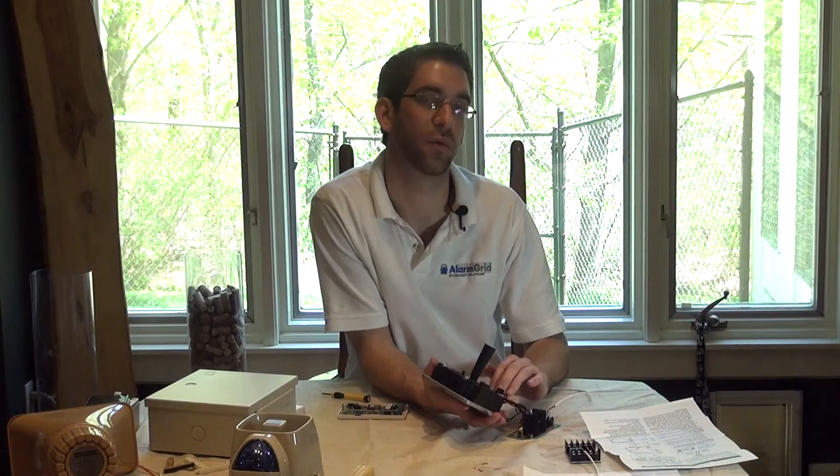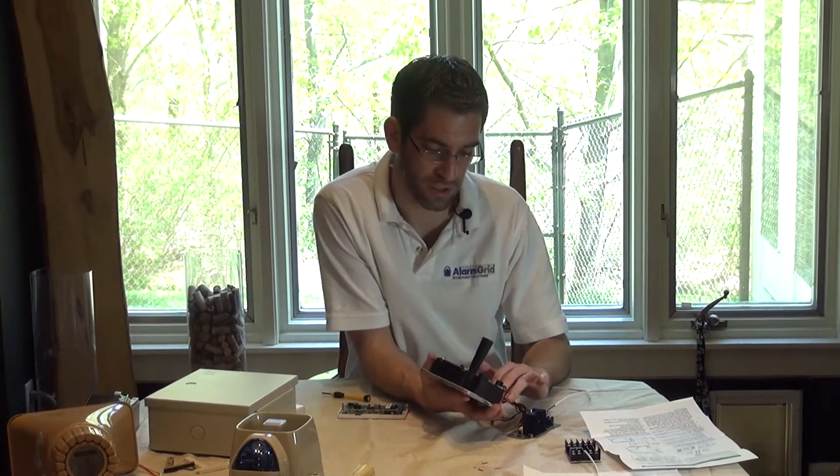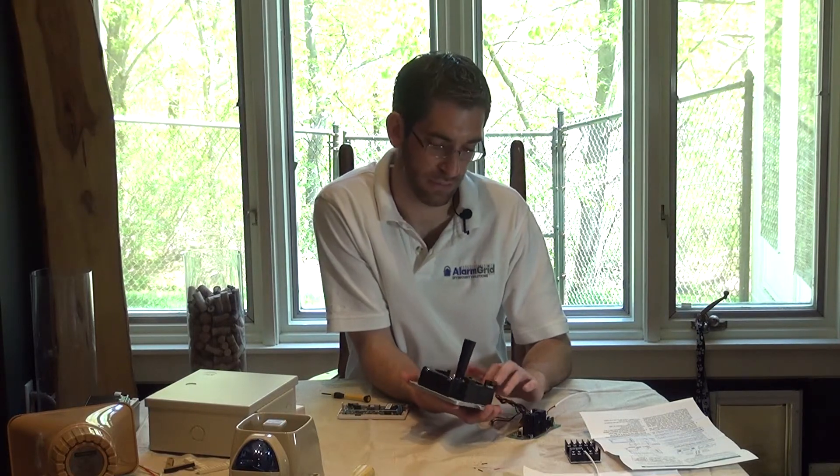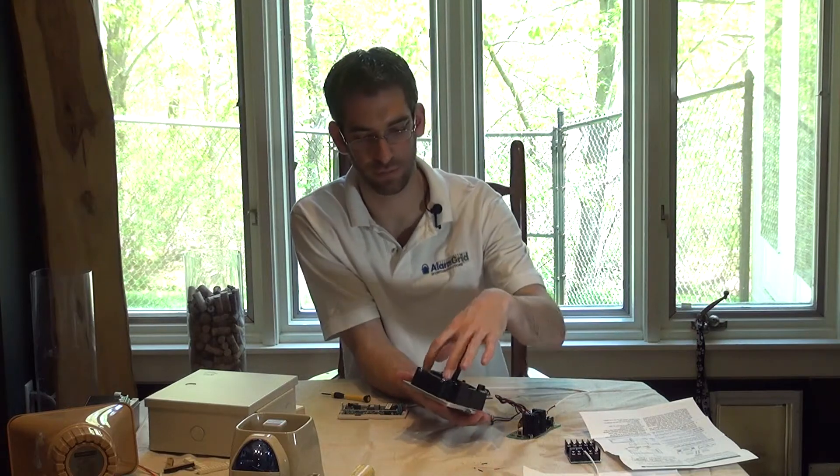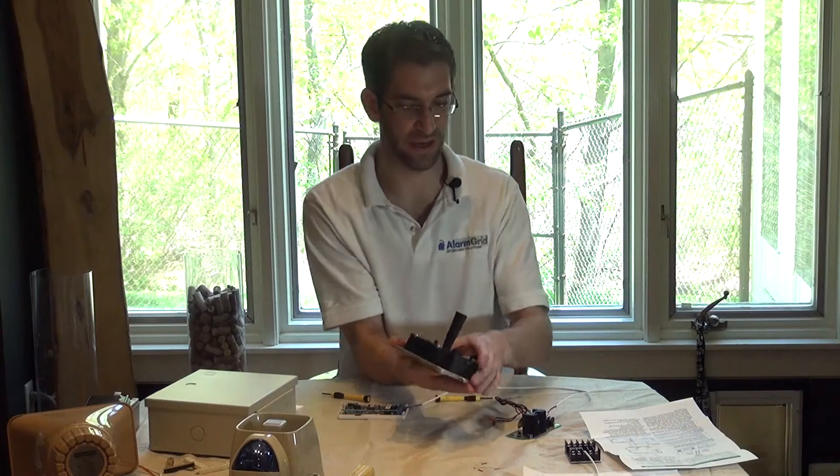The tamper will go to a zone. You could use the hardwired zone of the control panel. Most people don't, especially in a residential application, don't bother with the tamper, but that's what those terminals are. So, we're going to now make our connections from both the strobe and the siren back to our relay and our power supply.